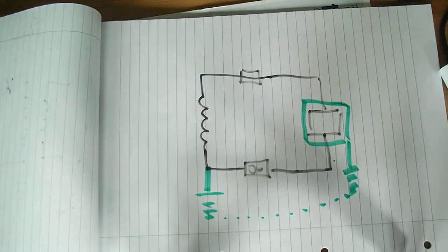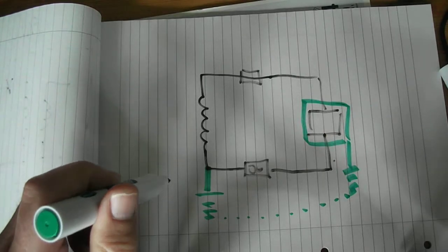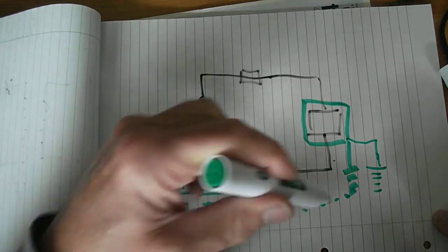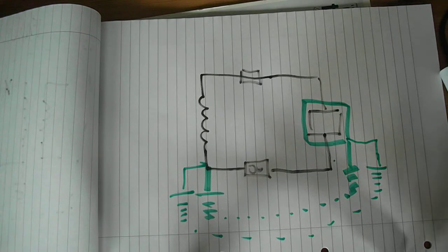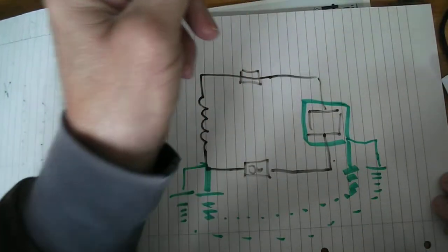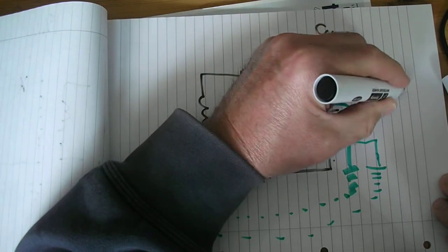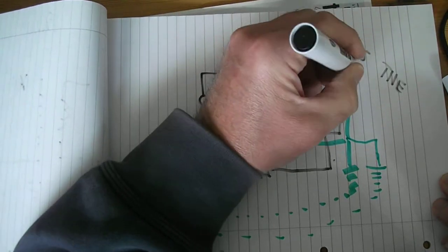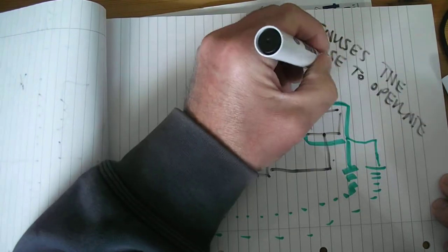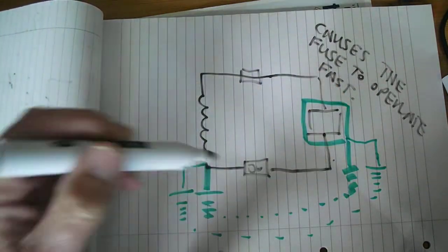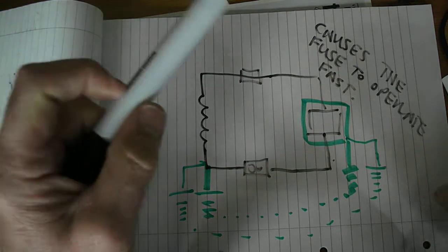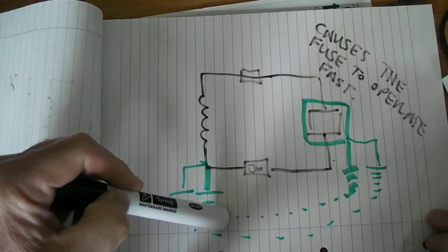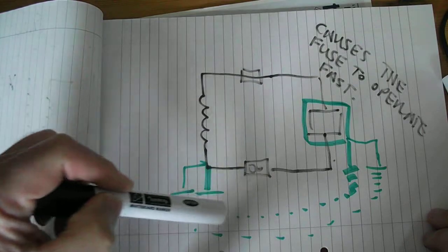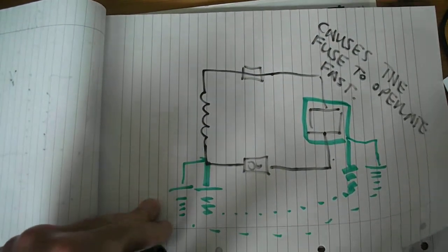Now, this resistance path here, from here to here through the ground, has to be as low as possible. And if it's too high, you can lower it by putting extra electrodes into the ground at either end, creating more parallel paths, which lowers the resistance. So we have to have a low resistance between those 2 points, because it causes the fuse or circuit breaker to operate fast, and that's why that has to be a low resistance path. So you might get questions on what's the important thing about these 2 electrode points, and the idea is that the resistance path has to be as low as possible. Okay.